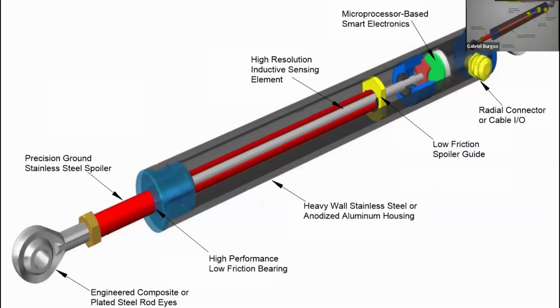And the signal that comes out is, of course, some fraction of that. Most LVDTs are somewhere between 4-to-1 and 6-to-1 ratios between the primary and the secondary. So you can see there are some differences. This one has a coil, but it's excited at RF frequencies, 500 kilohertz up to maybe 7.5 megahertz. We'll talk about the electronics of that in a minute.